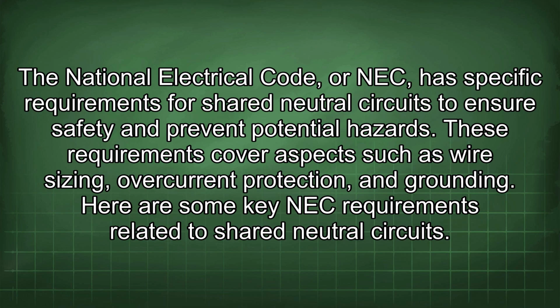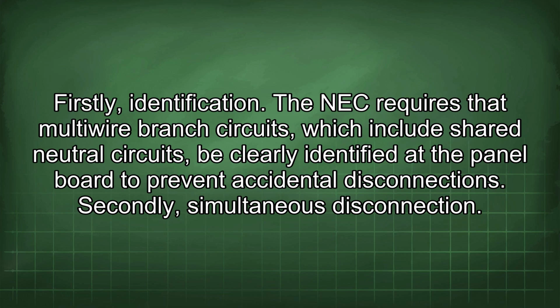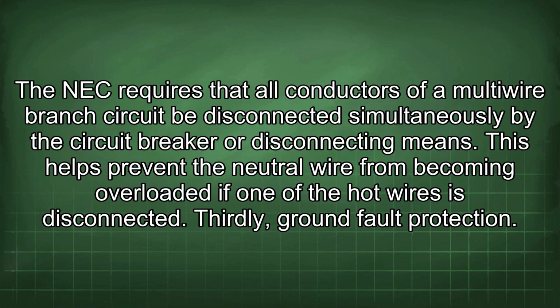The National Electrical Code, or NEC, has specific requirements for shared neutral circuits to ensure safety and prevent potential hazards. These requirements cover aspects such as wire sizing, overcurrent protection, and grounding. Here are some key NEC requirements related to shared neutral circuits. Firstly, identification. The NEC requires that multi-wire branch circuits, which include shared neutral circuits, be clearly identified at the panel board to prevent accidental disconnections. Secondly, simultaneous disconnection. The NEC requires that all conductors of a multi-wire branch circuit be disconnected simultaneously by the circuit breaker or disconnecting means. This helps prevent the neutral wire from becoming overloaded if one of the hot wires is disconnected.